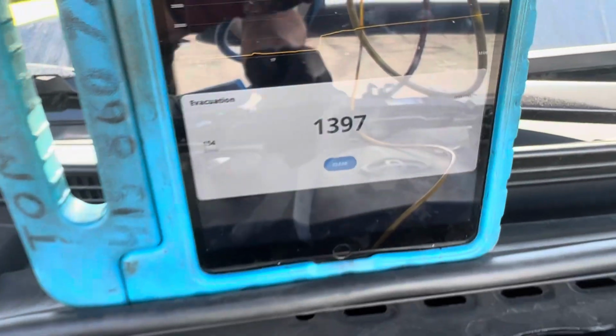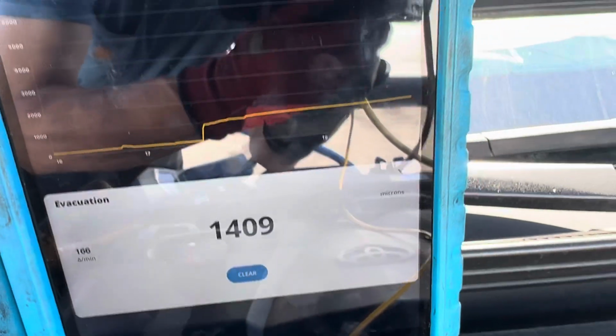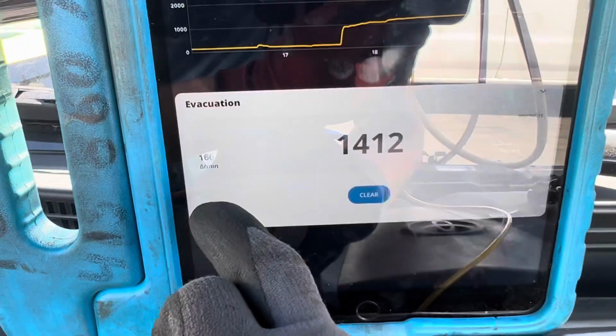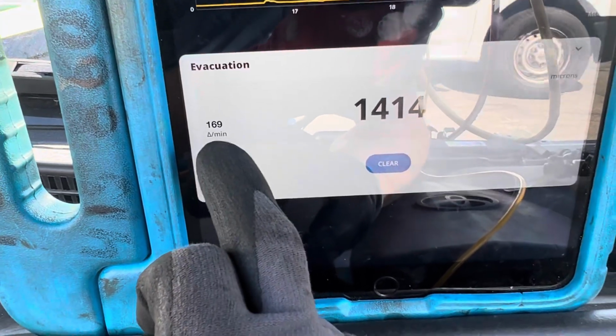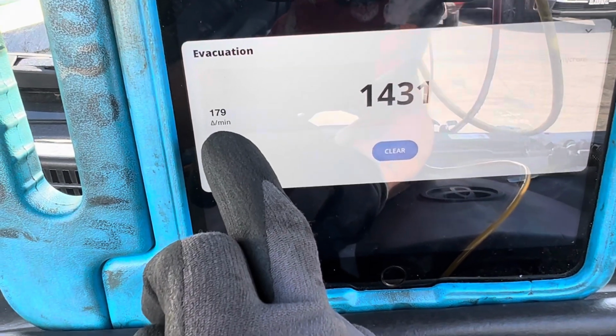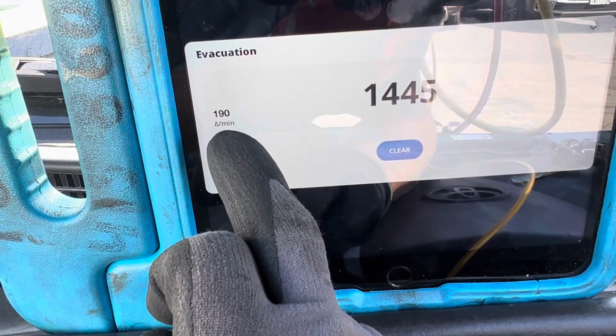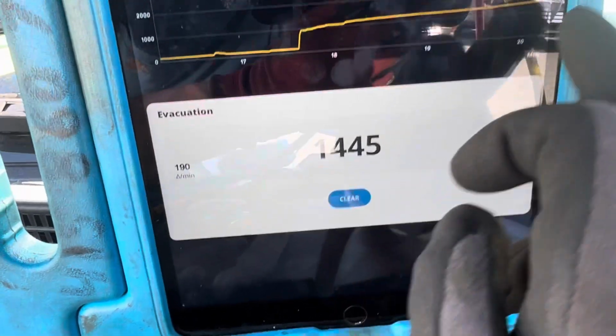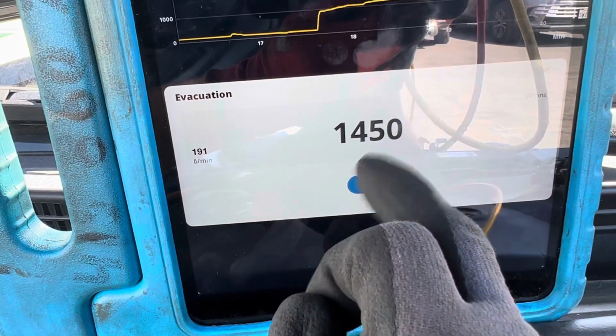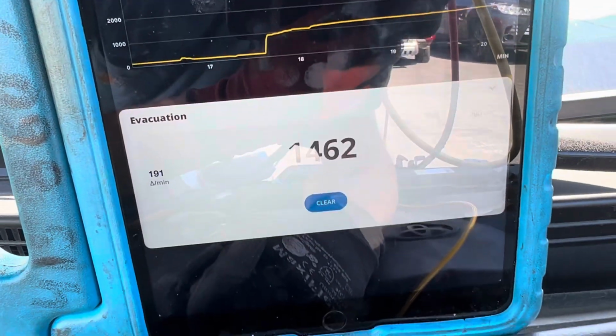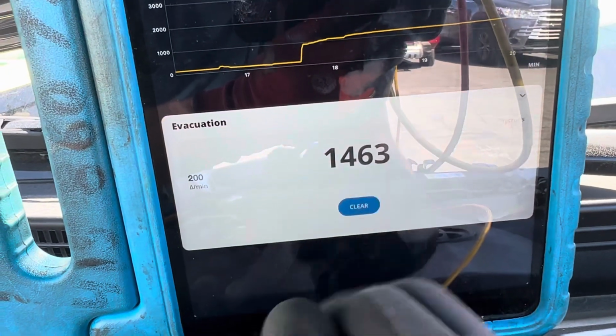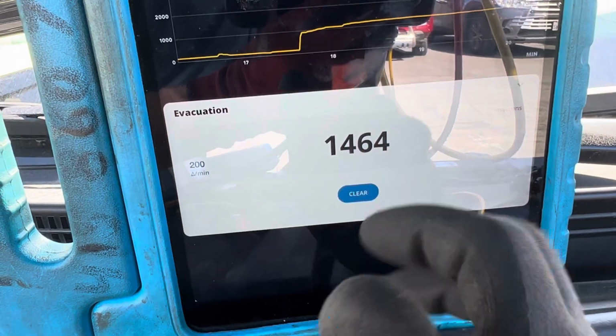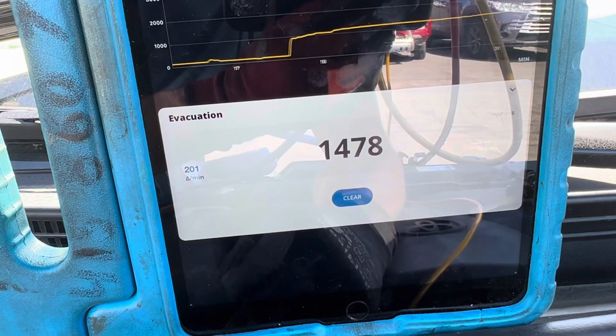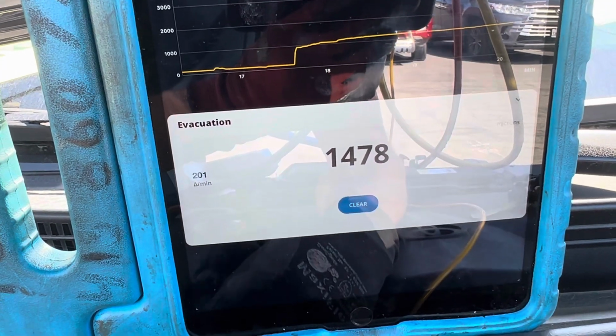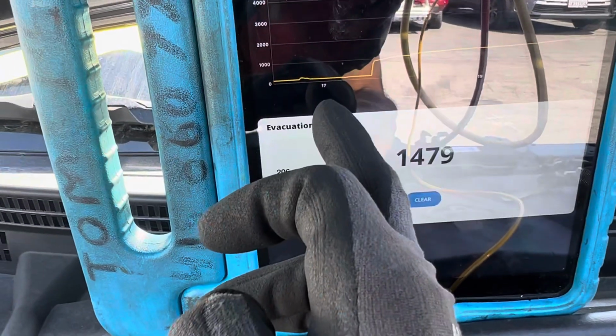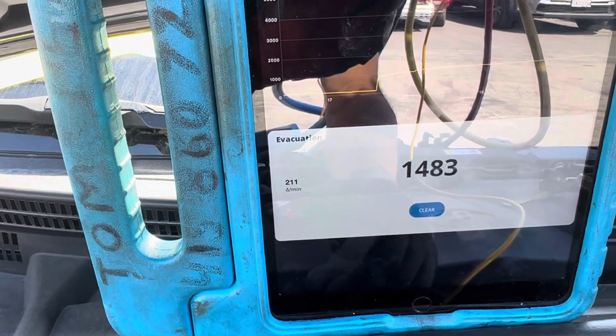So here we go, we're getting there. As you can see, we're no longer like 240 microns a minute, we're down to 100 and almost 80, 90. We're starting to slow down, but we're getting to that 1,500 micron level. Eventually, after 10 or 15 minutes, what I said - I was guesstimating about 1,500 microns - it looks like it's going to shoot up more towards 1,800, but I only have 17 minutes of additional vacuum on there.